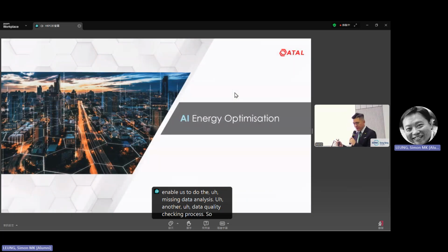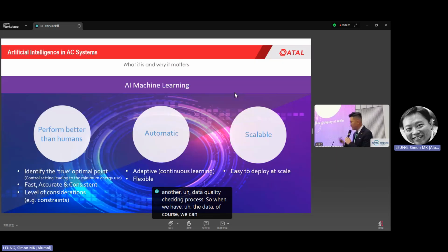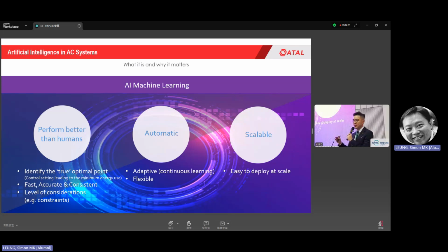So when we have the data, of course, we can let the AI do the energy optimization. Why is AI better? Simply because it can help us find the optimum control setting based on a particular cooling mode and weather condition. What does optimum control setting mean? It means that setting will minimize the energy use of the whole chiller plant or whole HVAC system.